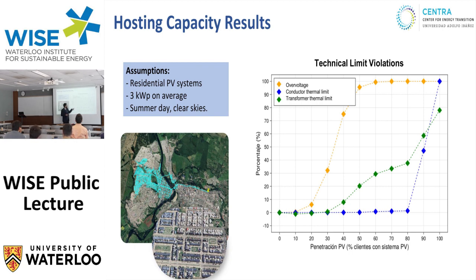As you add penetration of photovoltaic, at some point you hit over-voltage limits, shown by the yellow line—after 10% you start hitting voltage limits. After 30%, you start hitting transformer thermal limits, and eventually conductor thermal limits, though that's rare. Here, 10% means 10% of consumers having photovoltaic systems, not 10% of peak load—it's actually nearly 60% of the peak load.